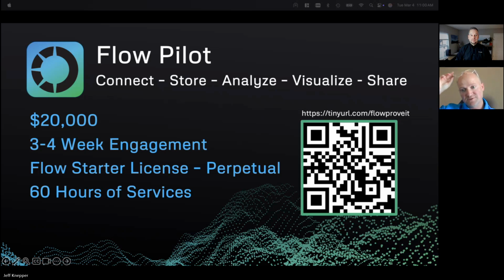Another important thing to notice as well is that if I already have the hourly data contextualized within Flow and I want to get a daily or a weekly number, we're not going to hit the historian again. We hit the already aggregated data in the Flow database. So we really try to optimize that process of collecting data from source, trying not to overload that system, and utilize the aggregations that we already got to further the calculation stream or dependency stream upstream. So it's really efficient in the design as well.